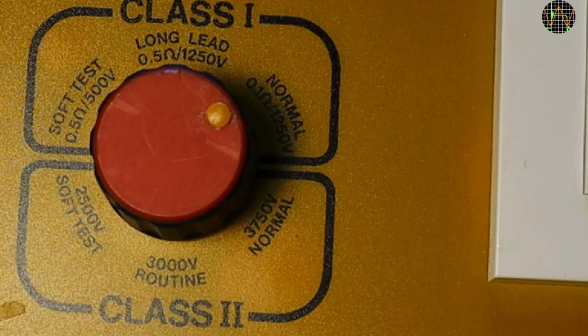Class 2 doesn't have an earth connection, so there is no test for that, only for high voltage insulation. And boy, even the soft test uses 2500 volts. The position labeled routine ups that to 3000 volts and the normal position to 3750 volts. And these are all AC RMS values, so the peak voltage at 3750 volts is almost 5300 volts. Wow! Even soft will very likely destroy whatever modern equipment you plug into here. Was this machine built for a different standard, or maybe an older standard? If anyone knows, please leave a comment.